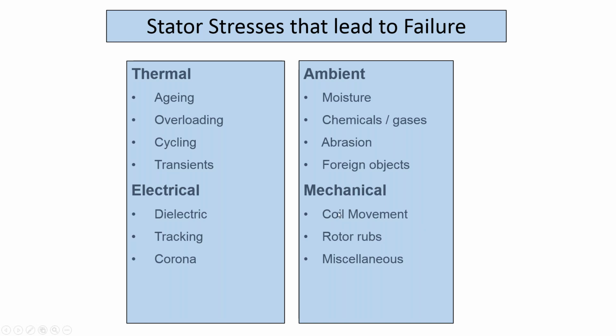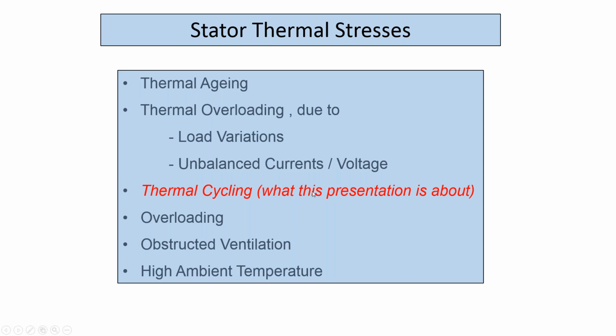So in any electrical machine, you're going to have thermal cycling and coil movement. It'll vary. Some motors, like for example, petrochemical motors, Sasol, will be designed to switch on and run continuously for 4 years. Others stop and start every hour. There, the thermal cycling is what this presentation is about, and the point is that it does still depend on your voltage stress across the insulation. So if you put X amount of mechanical stress on insulation that is sitting at 5 kV per millimeter, and the same amount of stress on insulation that is sitting at 1 kV per millimeter, you're obviously going to get a different time to failure.